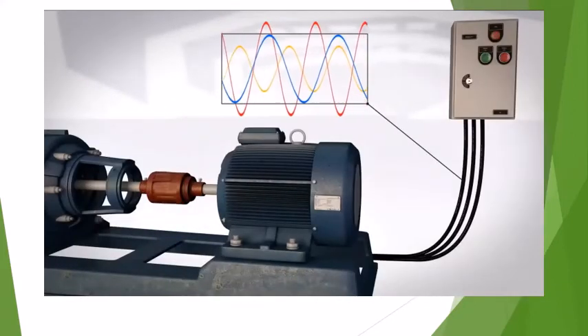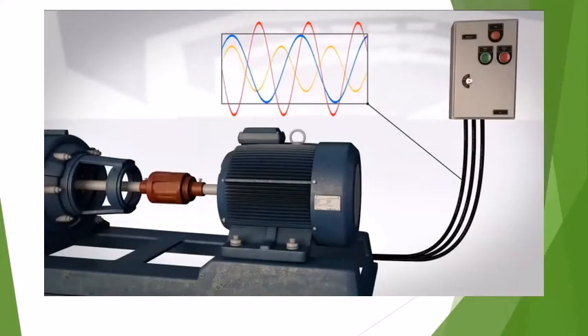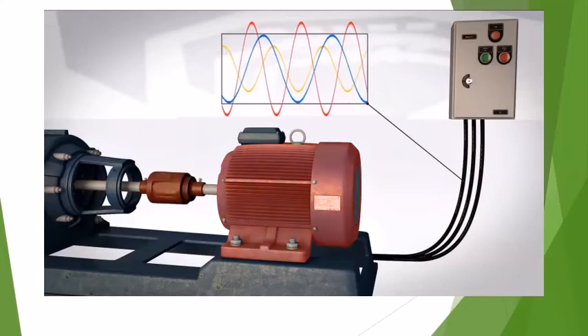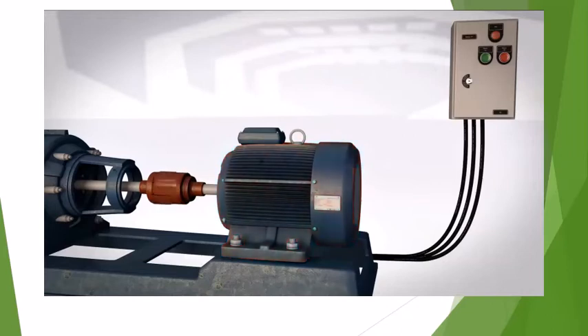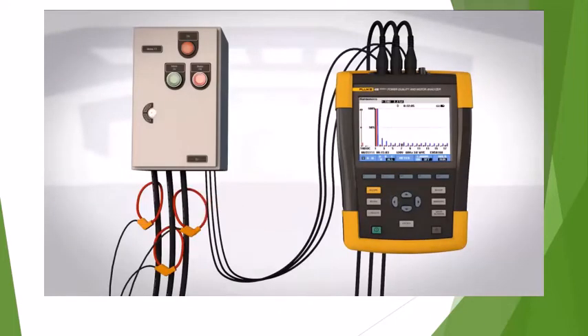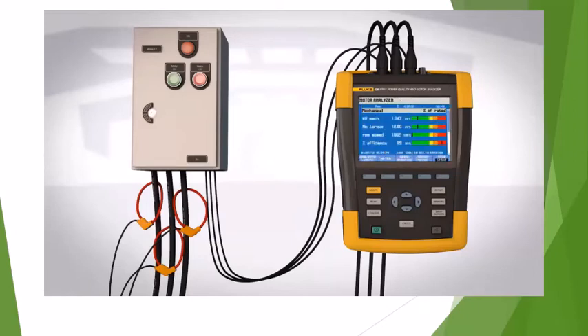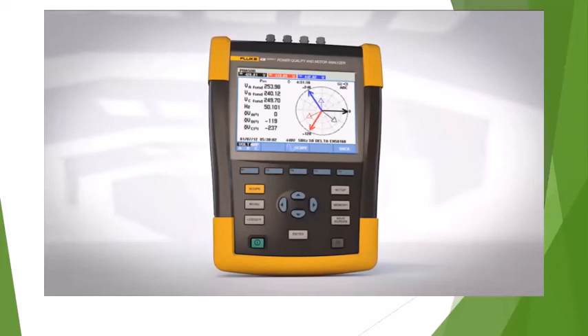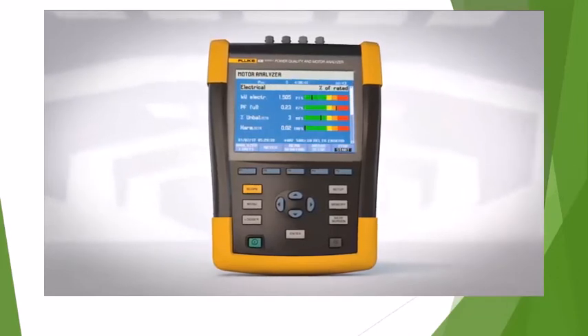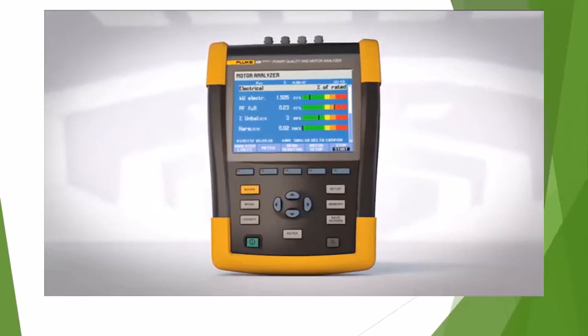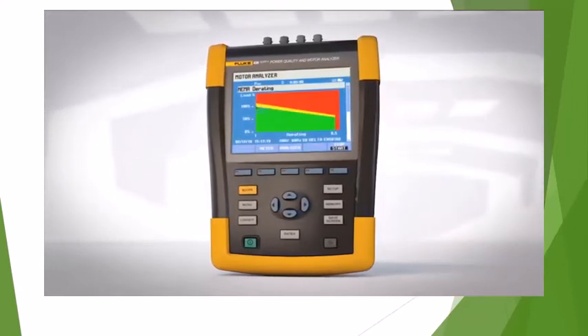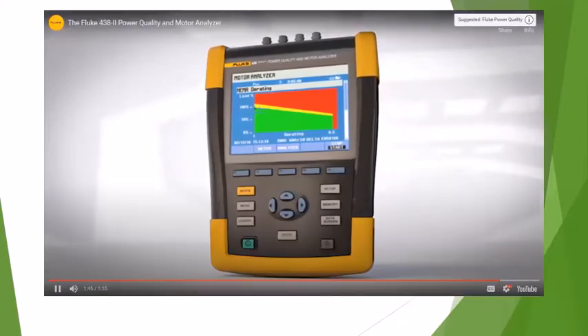Power quality issues, such as unbalance and harmonics, can cause motors to run hot, eventually stressing windings and accelerating failures. Motor failures lead to costly downtime, and the cost of waste associated with inefficient motors adds up. When testing direct online motors with the new Fluke 438, you get both power quality information and mechanical performance data in the same test with a single tool. With an intuitive user interface, optimized current probes, and at-a-glance motor status screens, the Fluke 438 gives you the motor troubleshooting information you need to make better maintenance decisions and keep your plant up and running.